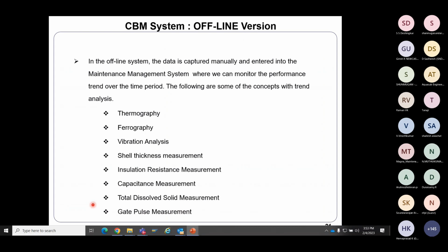It is not just vibration measurement. First, you start with the vibration measurement, then you get into the vibration analysis, by which you can identify by what phenomena this particular vibration has been exceeded. Then shell thickness measurement, which we can do with UT sensors, and insulation resistance measurement, which obviously every one of us will do.